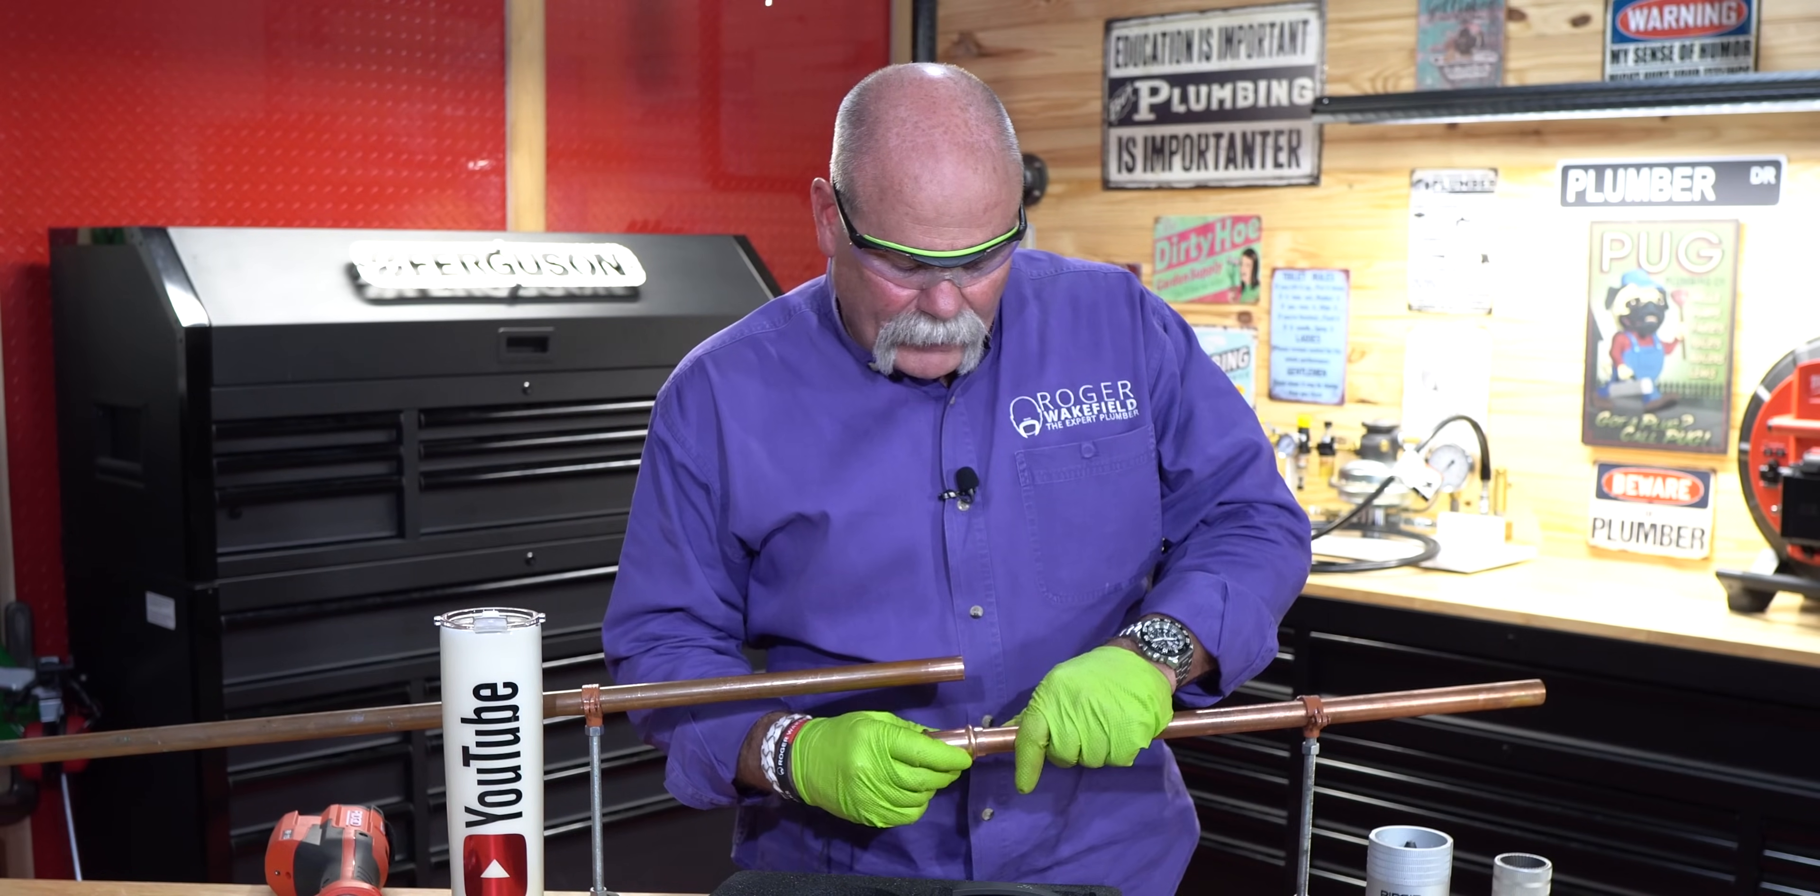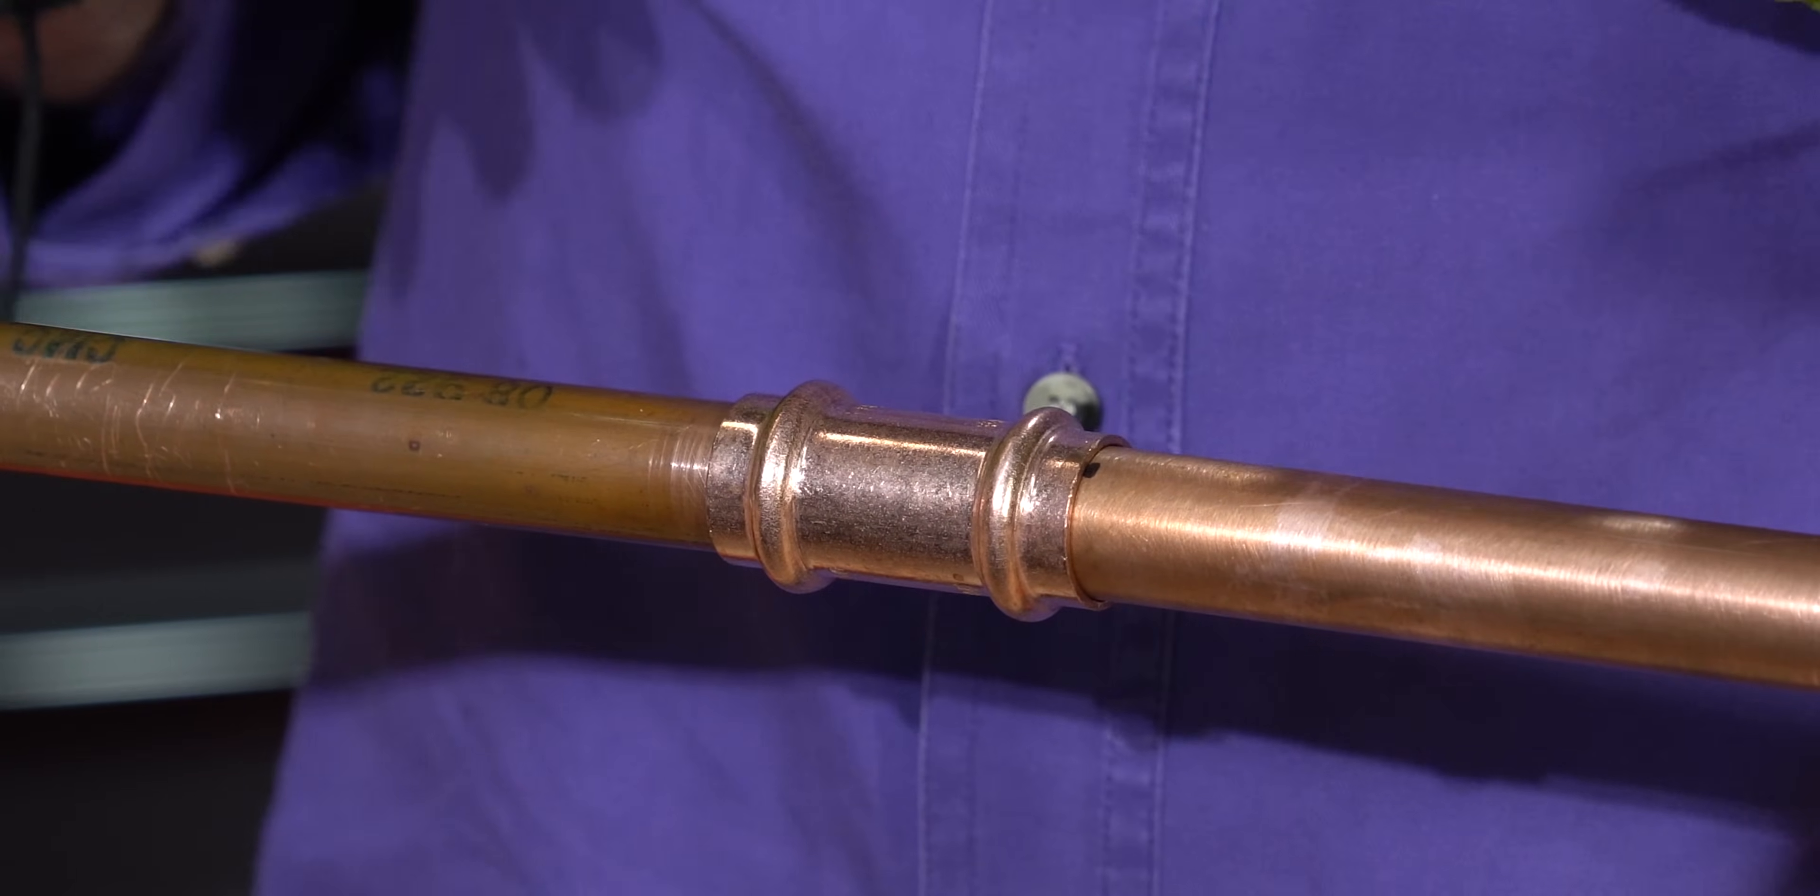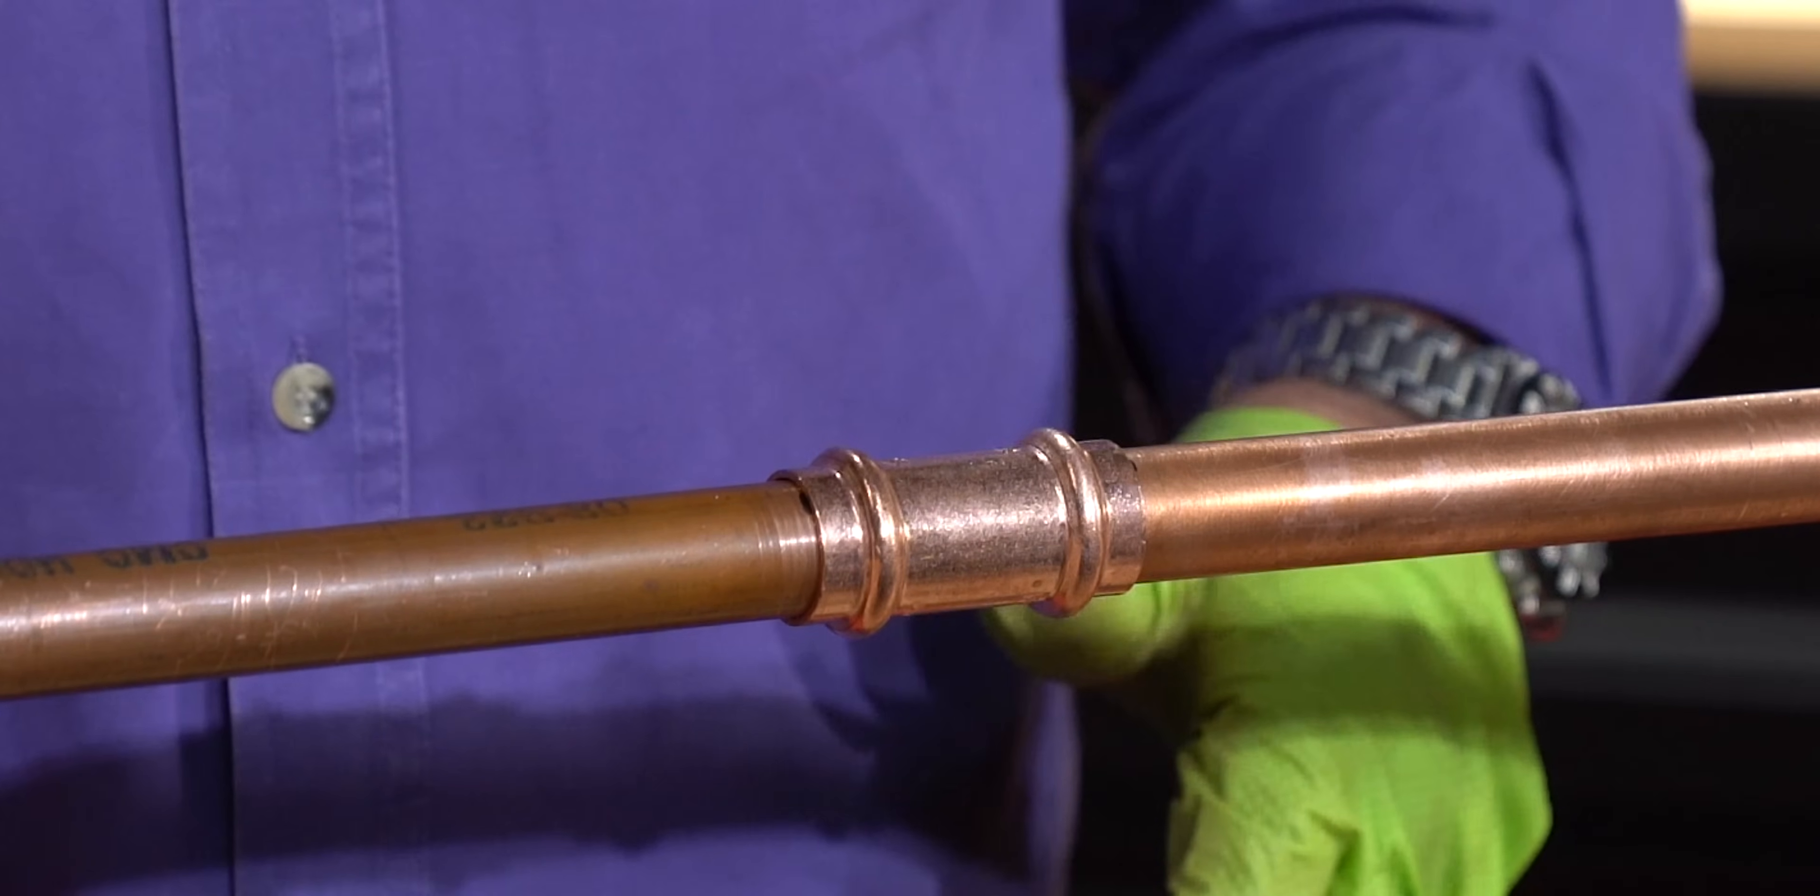I'm going to go ahead and put my first side together and go right up to that mark. And then I'm going to do the same thing here. And now that I'm in, I'm going to center my fitting on those marks. I know that where I marked it, I now have this in right where I want it to be. Now, this has a 210 degree angle on rotation here. So I don't have to be perfectly lined up, perfectly square. I could get in a weird position, get in an overhead spot where I might not normally be able to get to something. I've got everything set where I want it.